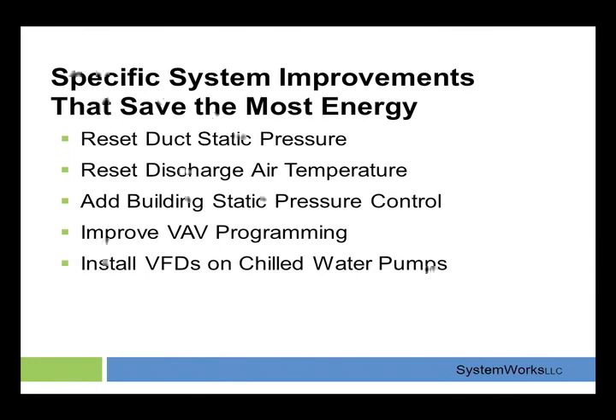When you were a little kid, if you remember putting your finger over the end of the hose, if you blocked off 70% of the hose, you got a real fine stream of water, but you created a tremendous amount of resistance or pressure on your thumb. That's what's happening to those pumps. Those pumps are spinning using a large amount of energy and creating a small stream of water. When we put the VFD on them, we're able to open those valves all the way up, let the motor slow down, and save a huge amount of energy.